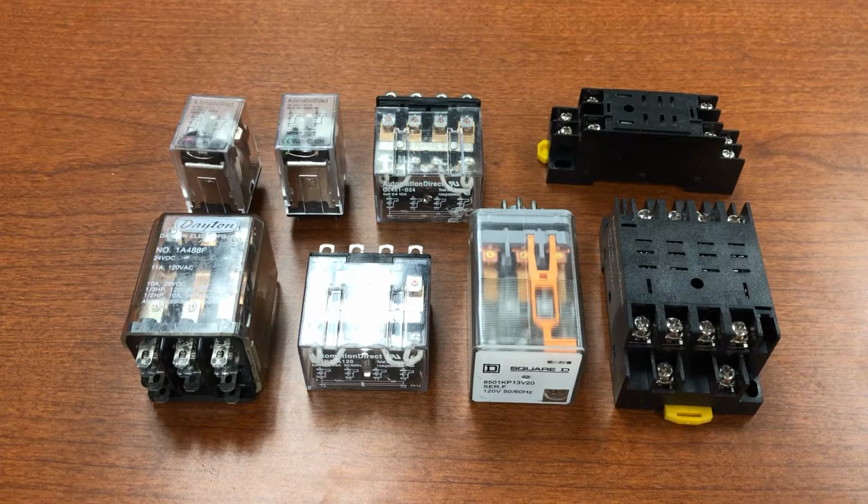So a relay or control relay is basically a solenoid that has contacts attached to it, so that we control the current to the coil, and when we apply that current, that creates a magnetic field that changes the state of the plunger inside, which moves the contacts to open and close those contacts. So here we're going to look at some different types and different configurations, read the information that's on them to better understand how they work, and so you'll know how to use these.